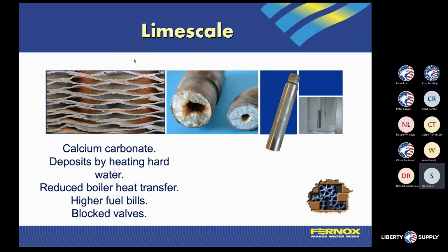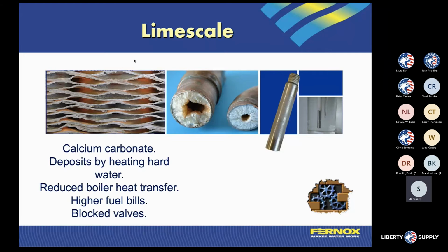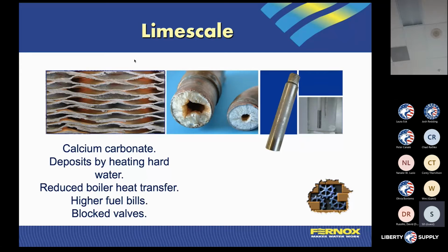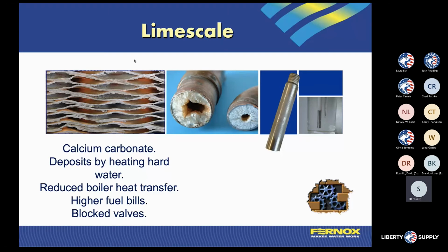We talk about lime scale. We're going to talk about the ability for the lime scale to come out of solution and plate to heated surfaces. So some of these pictures you're looking at are the byproduct of that, which is obviously reduced flow, blockages, and then potentially overheating of those different components. That's going to relate to costs of running the system, operation, and effective efficiencies, both in that your stack temperature will start to increase on a boiler system. You're also going to have longer run cycle times, which means all of those cases are going to create more cost on the fuel or the utilization side.